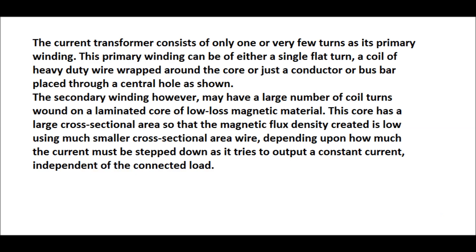The current transformer consists of only one or few turns as its primary winding. This primary winding can be of either a single flat turn, a coil of heavy duty wire wrapped around the core or just a conductor or bus bar placed through a center hole as shown in earlier figure.